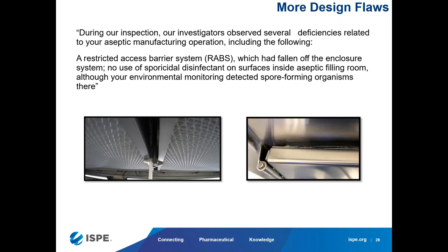There are simple solutions, and then you can get during cleaning. This kind of design then leads to eddy currents in smoke studies, which FDA is catching very fast nowadays, right? Plus, it can start contamination, spore-forming organisms, because you can't clean those gaps.